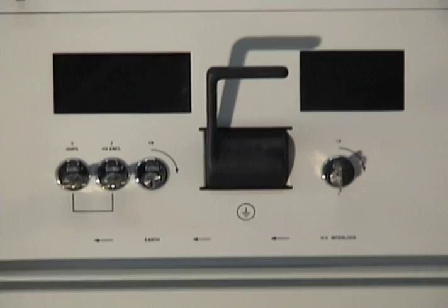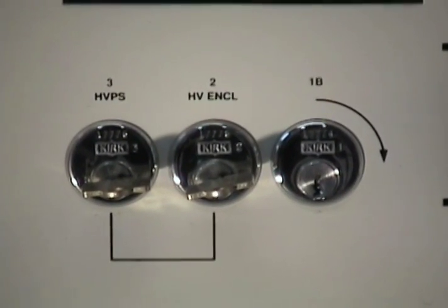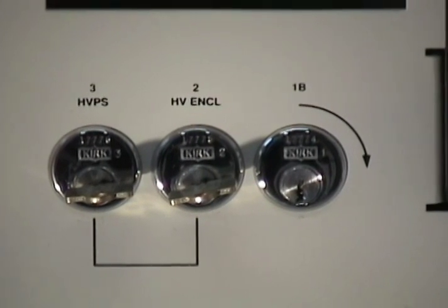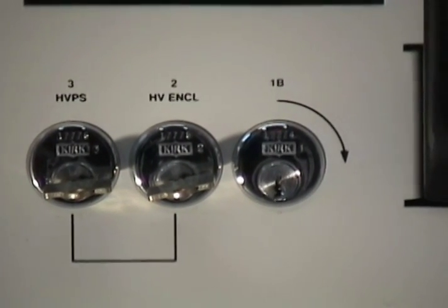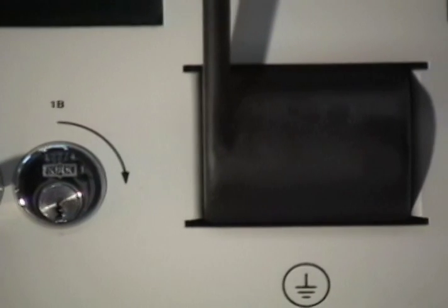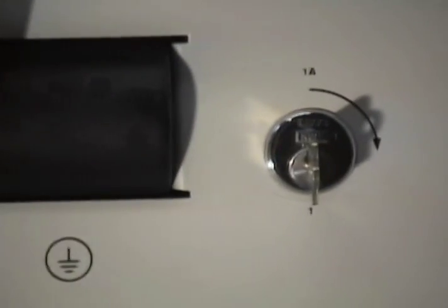Below all this is the high voltage interlock system, designed to prevent an engineer from coming in contact with any high voltage. The keys are used to prevent any compartments from being opened before they are grounded by actuating the grounding lever.